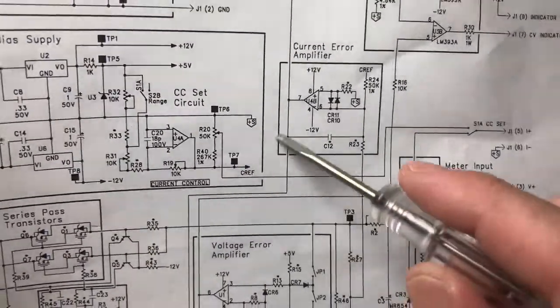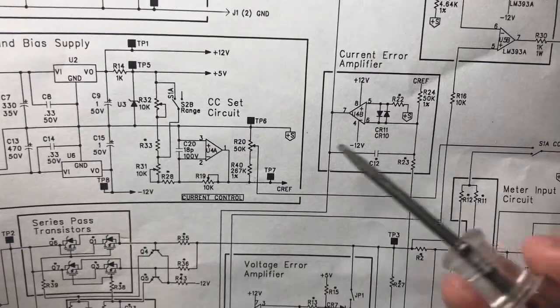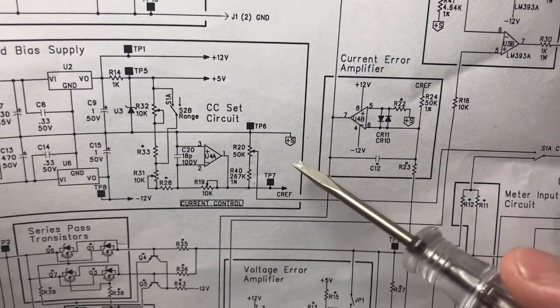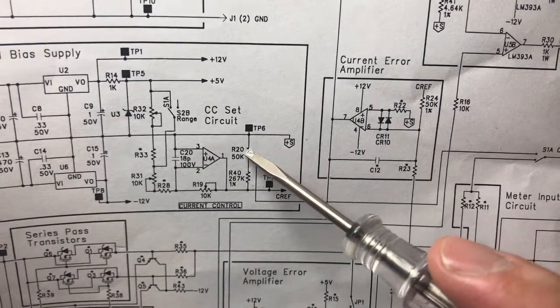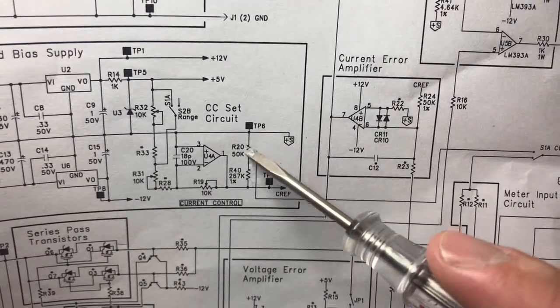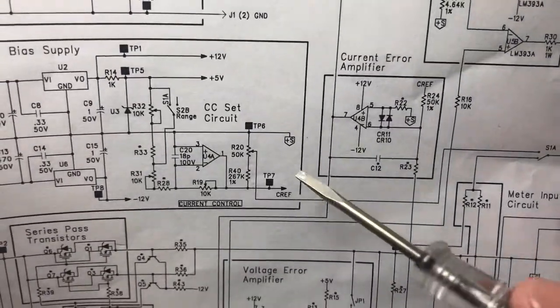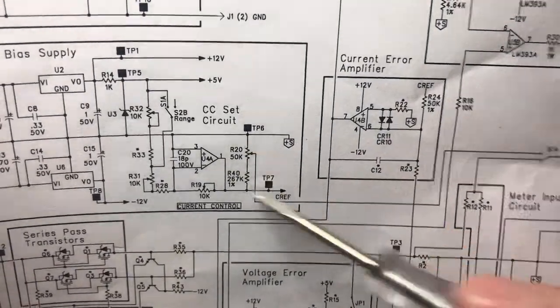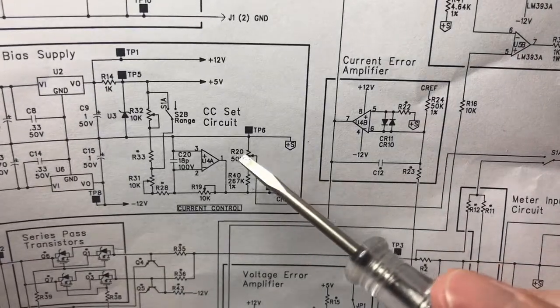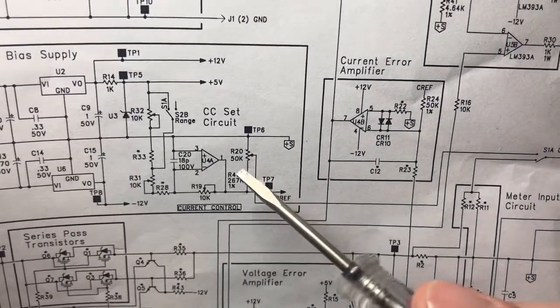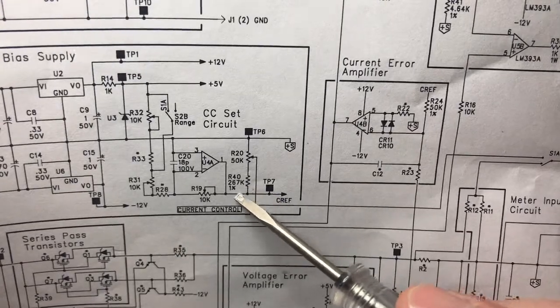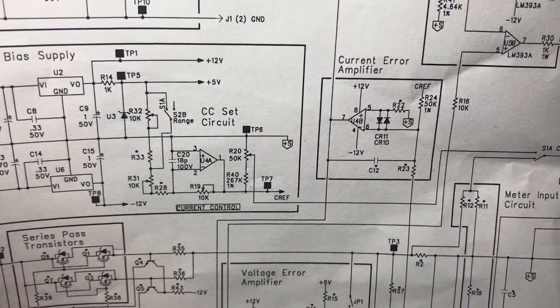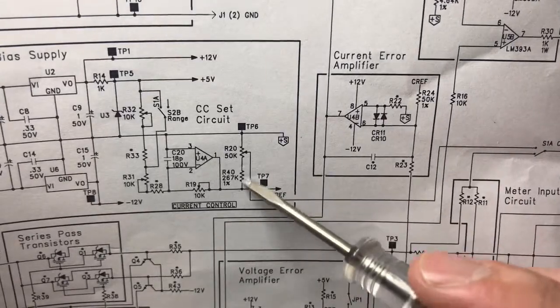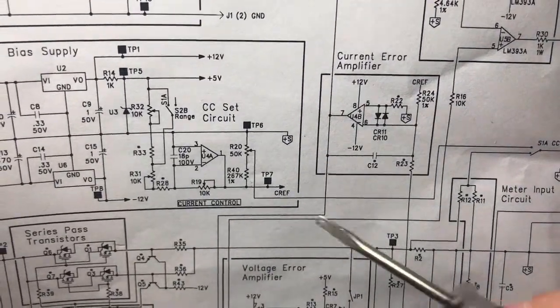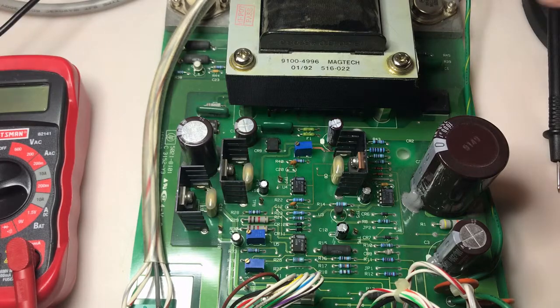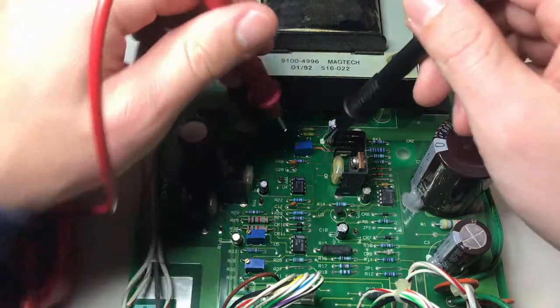So if we look at this specific part of the circuit here, there's only a few things really that could cause this. And so again, it's reading between positive S and the center tap of this potentiometer, which is right here. So really it's dependent upon the voltage drop across this right here. And so what could affect that? Well, the potentiometer itself, or theoretically R40. If this is defective in some way, that would definitely cause a difference in the voltage drop there. So let's take a look at R40. And it's way up here on the board.